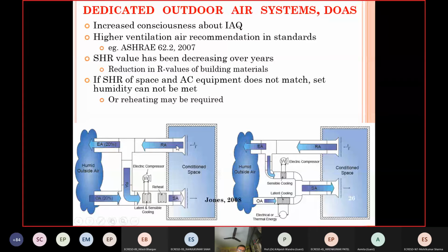So that's a waste. That is the energy that you utilized for cooling this air. It's going out, and so that energy is getting wasted. There is some recirculated air. Here it is shown that 20% is exhausted, so 20% is fresh or outdoor air, and 80% is recirculated, and you are mixing them in the mixing chamber. And then this is the conventional air conditioning system, and here latent and sensible cooling is done with the help of the conventional air conditioning system.